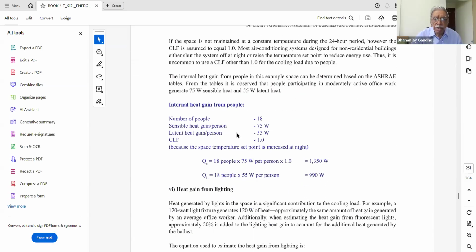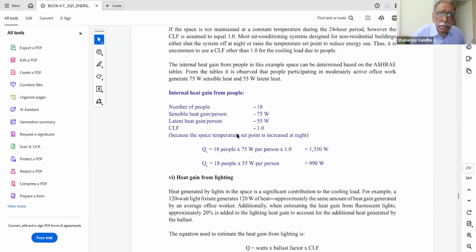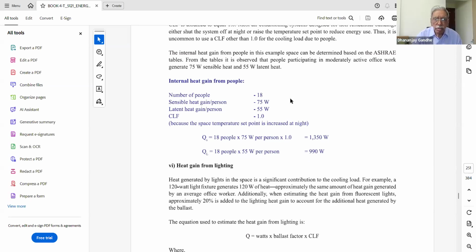Okay, so an example is solved over here. It mentions that the internal gain from people in this space can again be found using the ASHRAE standard tables, and from the tables it is observed that people participating in moderately active office work generate 75 watts of sensible heat and 55 watts of latent heat. Now, these are the standard figures which need to be considered for calculation of heat gain from people. In this particular area, in the earlier example, it was mentioned that 18 people are working in this room. So the sensible heat gain is 75 watt per person and latent heat is 55 watt per person. These are the standard ASHRAE values.